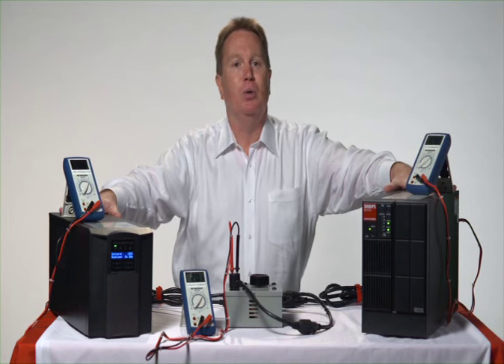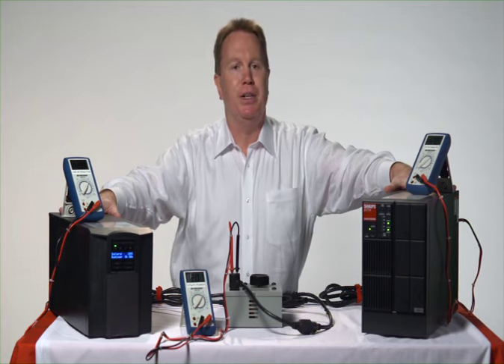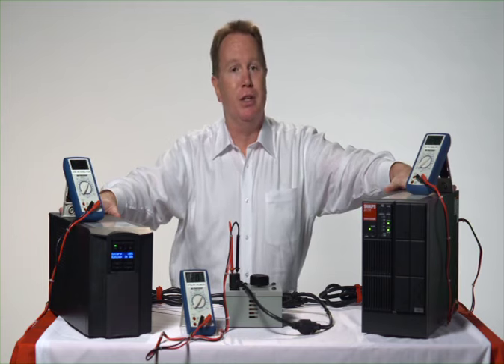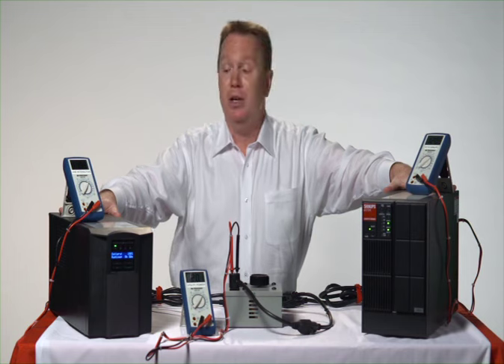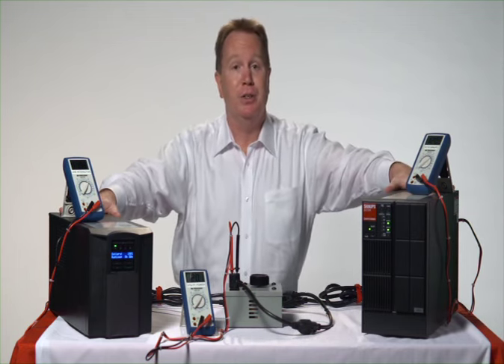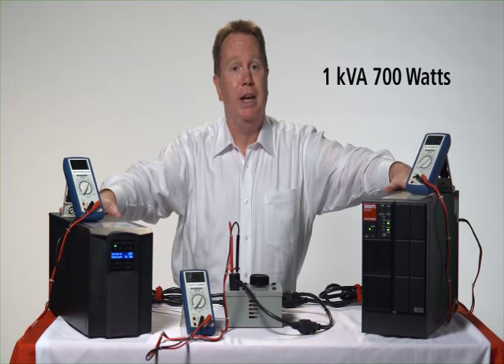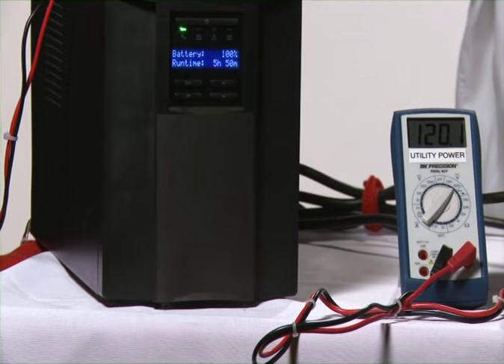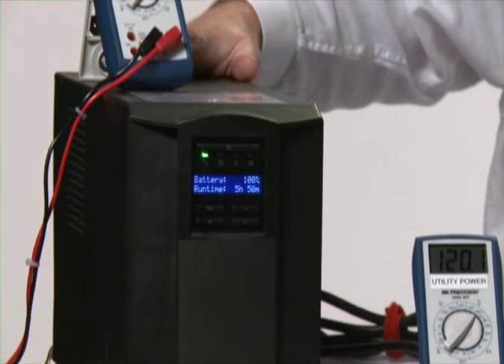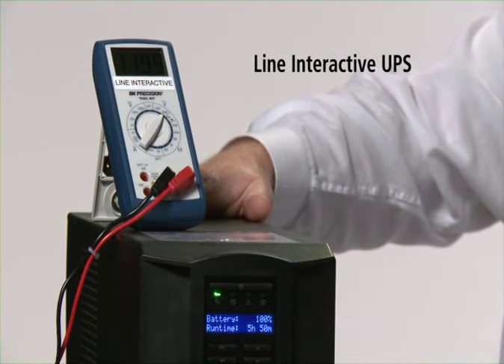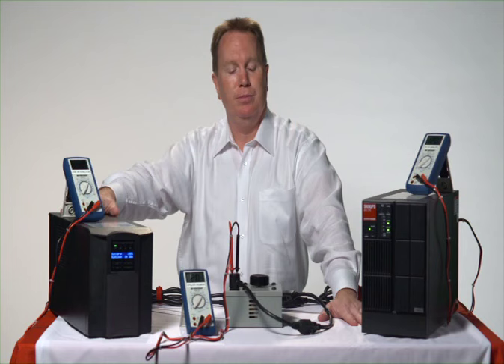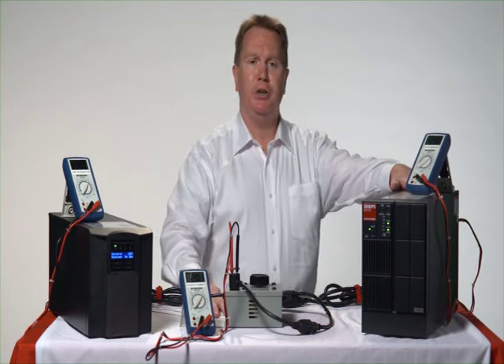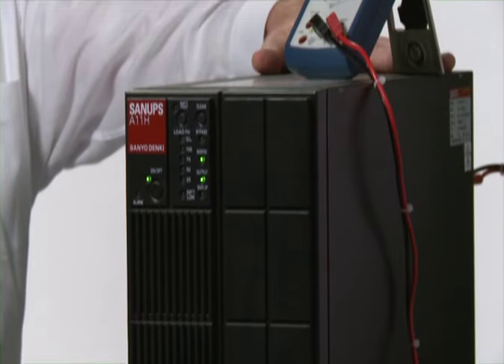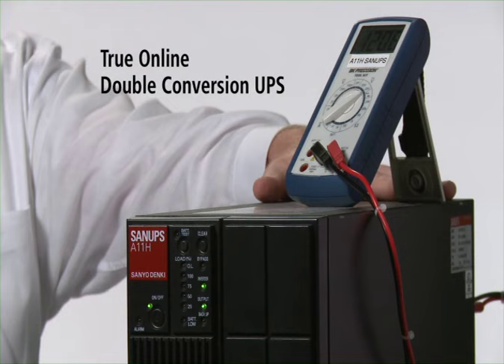In the next few minutes, we're going to demonstrate a dramatic difference in UPS output and their ability to deliver rock-solid, stable, clean, reliable, available voltage. Let's describe our equipment. We have two conventional single-phase UPSs, both of the same power, both 1 kVA, 700 watts. On this side, we have a current line interactive model of UPS. It represents the most advanced power design available on the market today. On this side, we have the SANYO DENKI America Sanups model A11H, also known as Sanups A. This is a true online double conversion UPS.